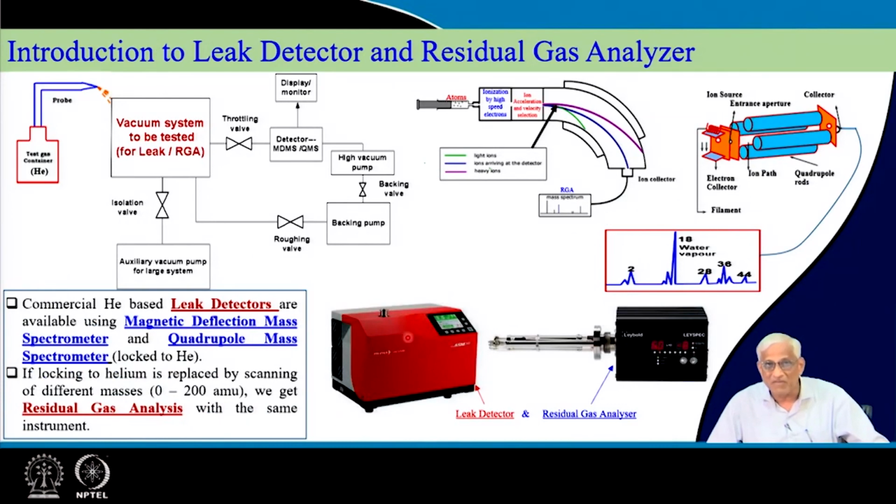This is magnetic deflection type of leak detector, totally dedicated for leak detection only. This is dedicated for residual gas analysis. By locking it to helium, you can use it in a leak detector mode. But a special mode cannot be a very sensitive mode. So, you have to keep both these instruments in the laboratory as essential accessories.